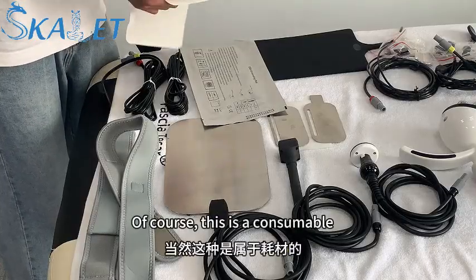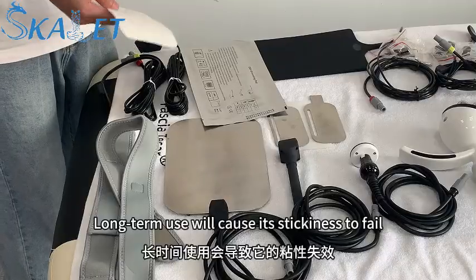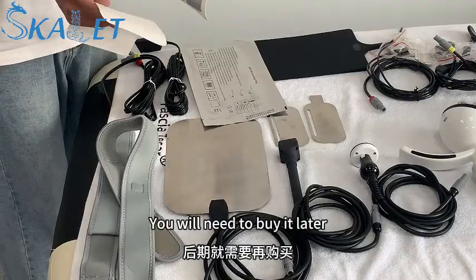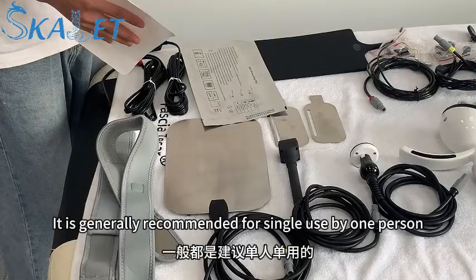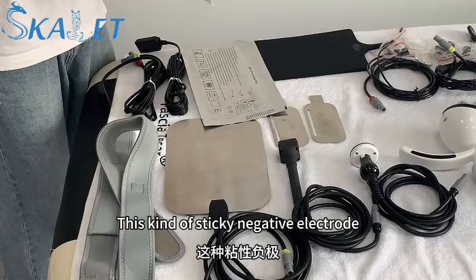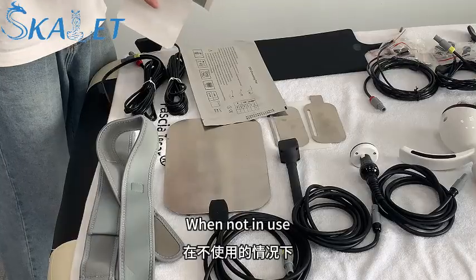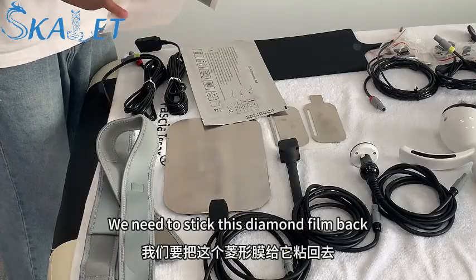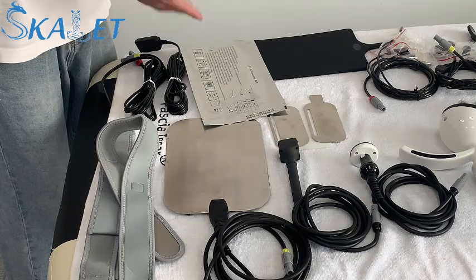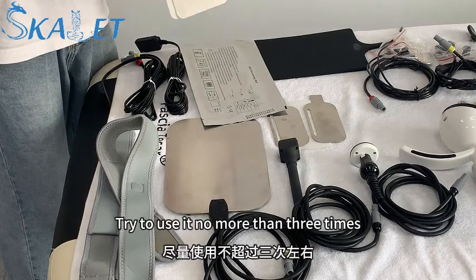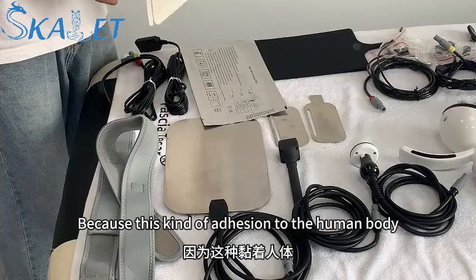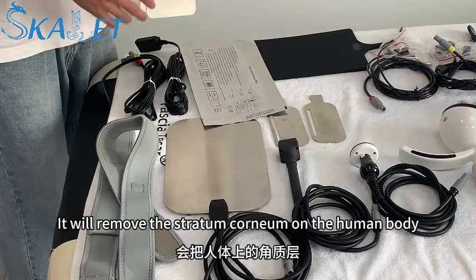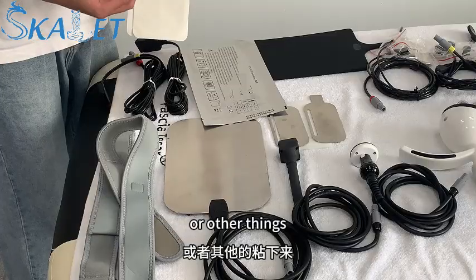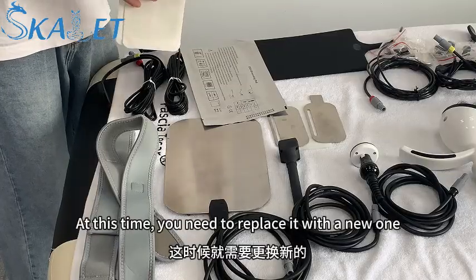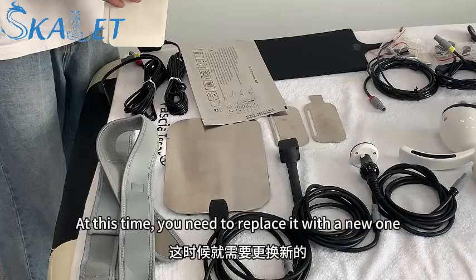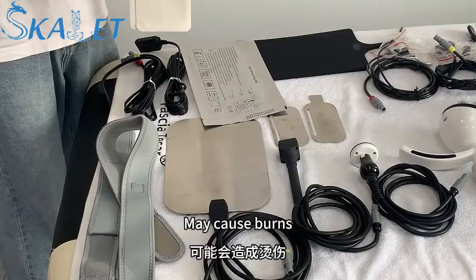Of course, this is a consumable. Long-term use will cause its stickiness to fail, and you will need to buy it later. It is generally recommended for single use by one person. When this kind of sticky negative electrode is not in use, make sure it stays sticky: we need to stick this diamond film back. Pay attention to this film. Try to use it no more than two or three times, because adhesion to the human body removes the stratum corneum and other things, and then the stickiness will weaken. At this time, you need to replace it with a new one when the stickiness is not enough, as it may cause burns or no energy.